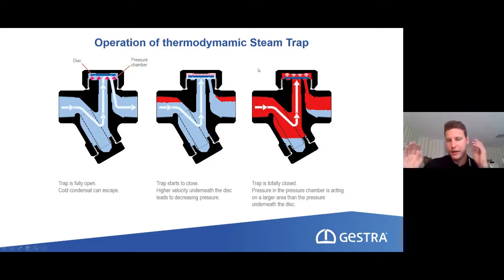And here we think of the two basic requirements we spoke about in the very beginning. The first one was that we don't like live steam losses. And here we have, let's say, a little amount of live steam that we're losing, because we need this high flow velocity so that the valve disc can detect there's steam and it has to close. This is not that much live steam, but we don't want a steam trap that is losing any live steam at all. The second disadvantage is that we have a metal-to-metal seat. If it's always clapping on the seat, you will not have good surfaces after 1.5 years, for instance. If we have any dirt particles or anything else, we get little scratches on the valve disc, and then we might lose some live steam, which we really don't want.